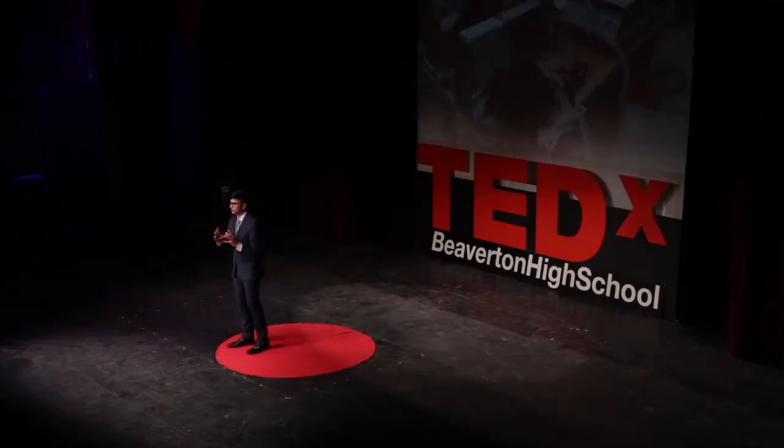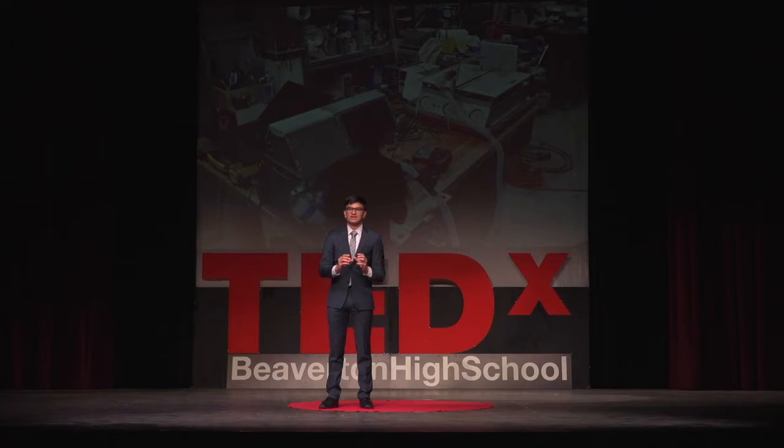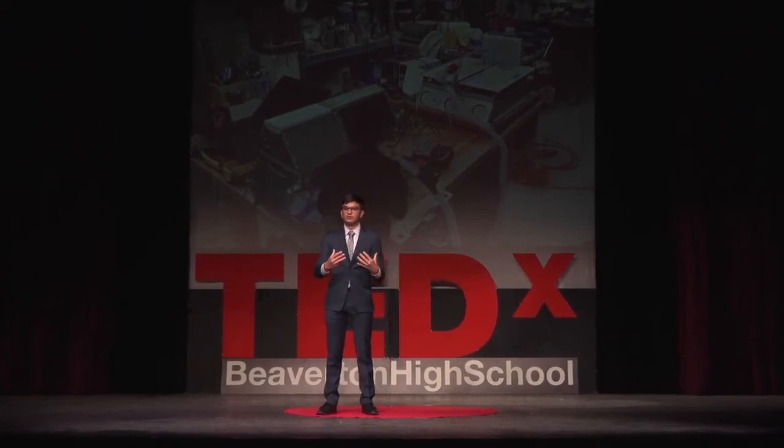I want to introduce you to an early prototype of what the LifeMech adaptive ventilation system looked like. As you can see, there's this gray box on the table — that's the LifeMech ventilator. You can see that black panel, which is a touchscreen that physicians can use to read out data from the product and to also input settings. Lastly, there's a bag that looks kind of like a balloon, but it's actually an ambu bag that's designed to push air into the patient. It's in these mechanical claws, and those claws squeeze air out through the tube and into the patient's lungs, which supports their breathing.